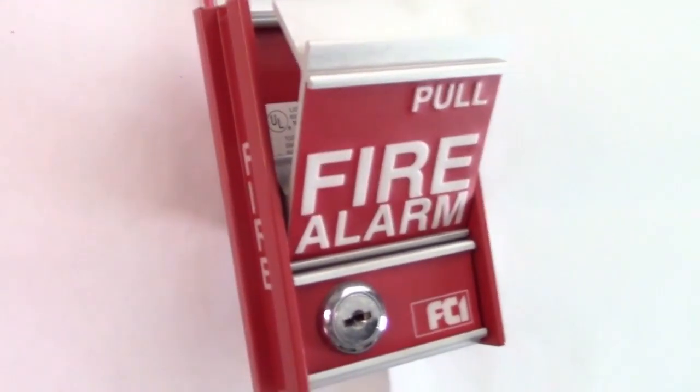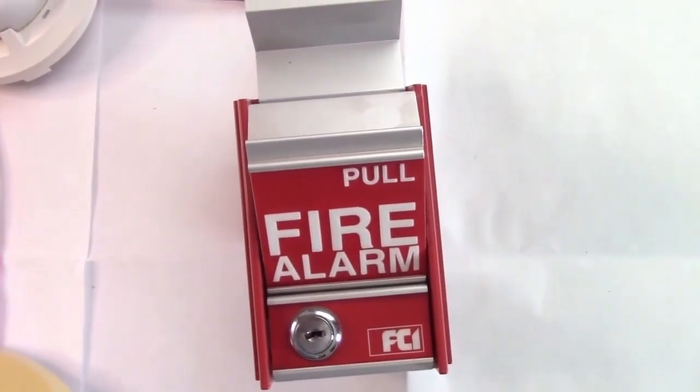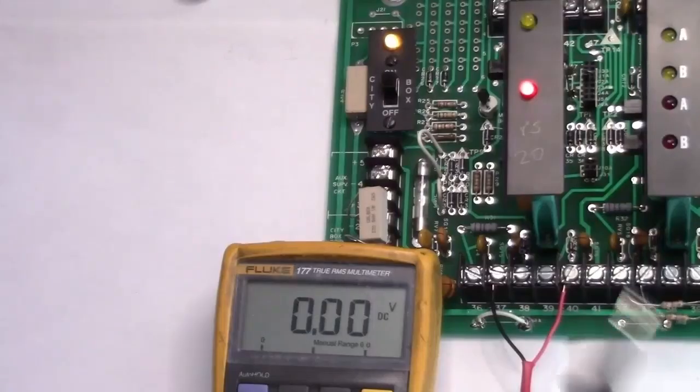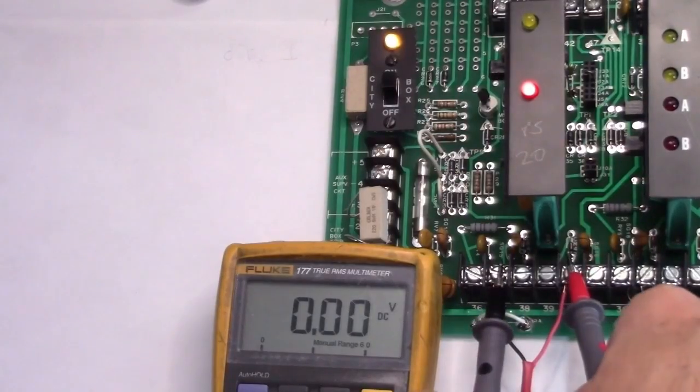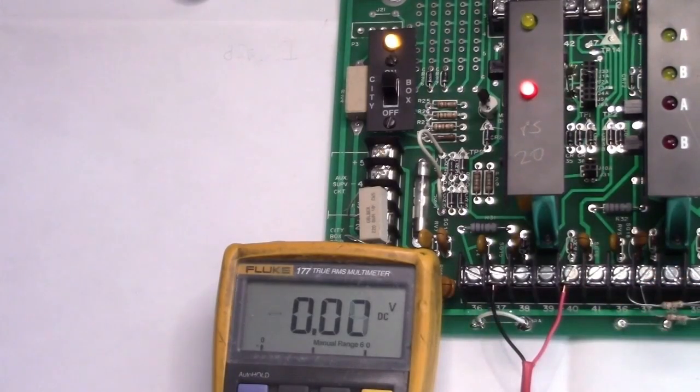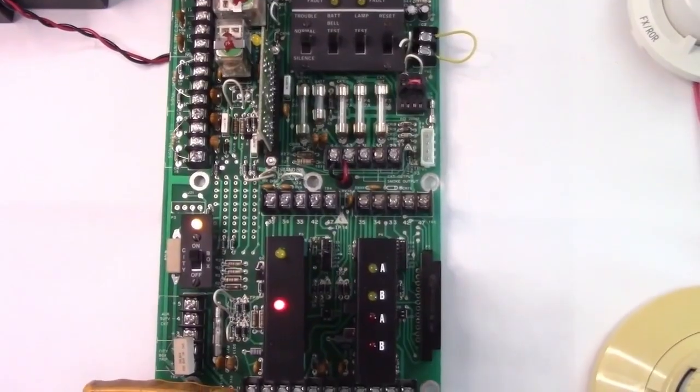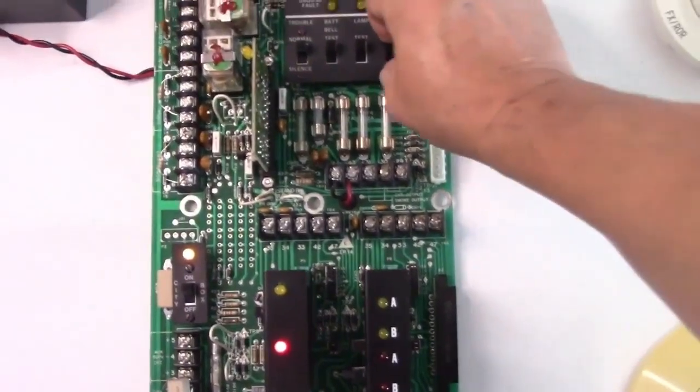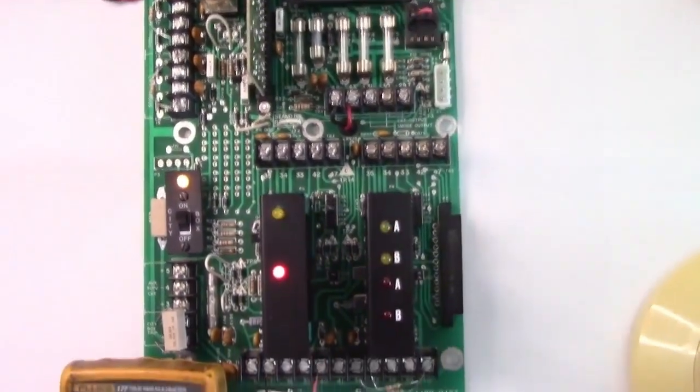Activating a pull station will put a short on the zone. We'll expect to read zero at the panel. Measuring across the terminals, you'll see that it is zero volts. That's how you know you're looking for a pull station, a heat detector, or a short in the wiring. You need to resolve the short before resetting. It'll just go right back into alarm if you don't.